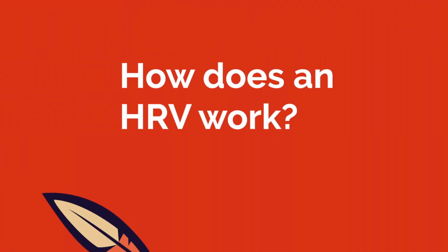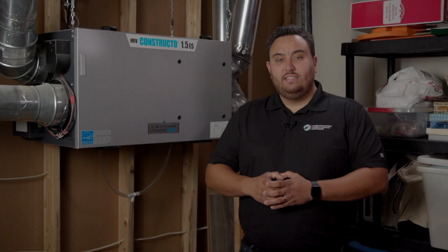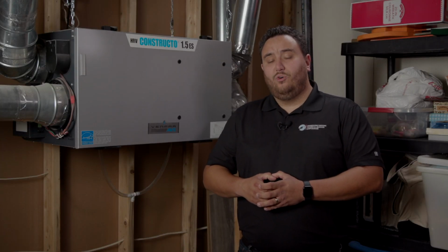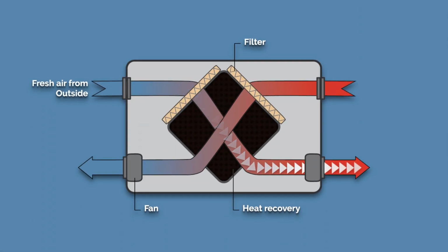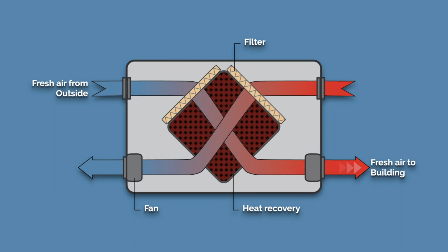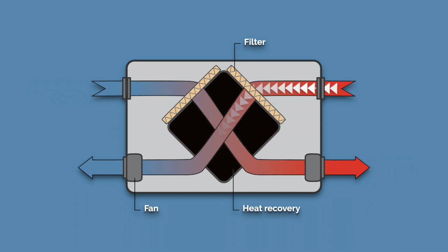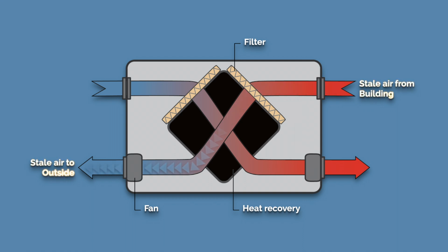How does an HRV work? During the heating season, an HRV exhausts stale, warm air to the outside and brings fresh air back into the home. As the air passes through the HRV, it warms the plates of the heat exchanger core. As clean, fresh outdoor air is supplied back into the house, it's warmed by the heat stored inside the heat exchanger core. An HRV can reverse this process during the cooling season, removing some heat from the incoming air and transferring it to the outgoing air.